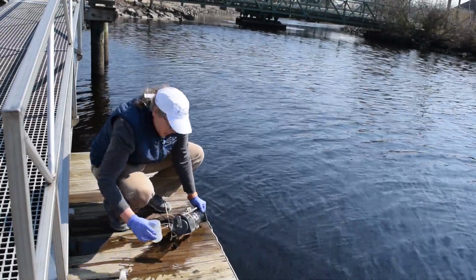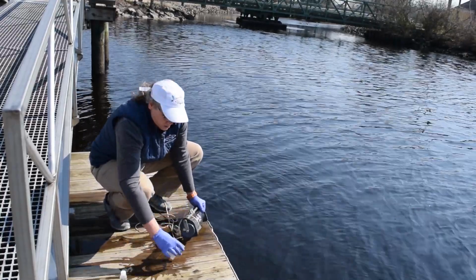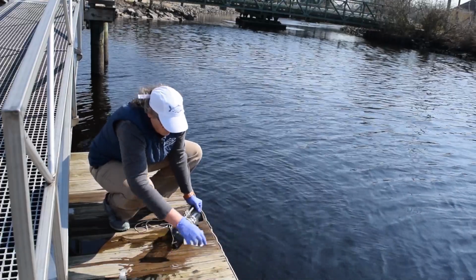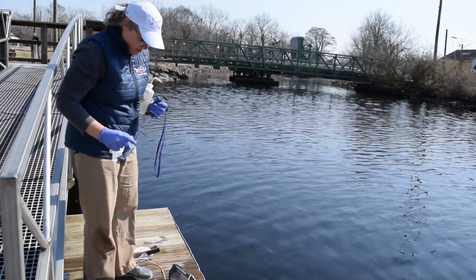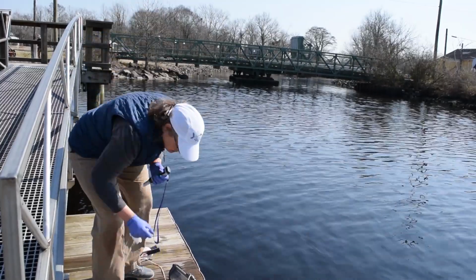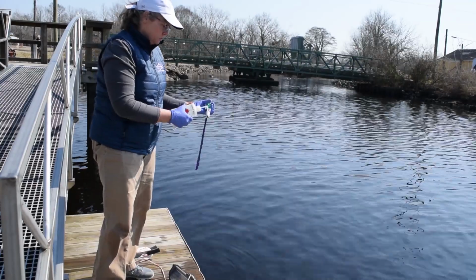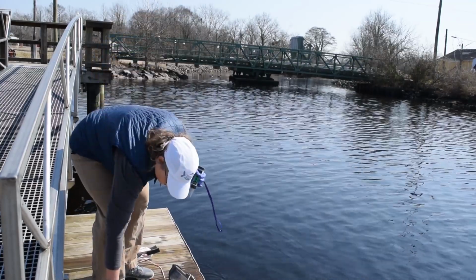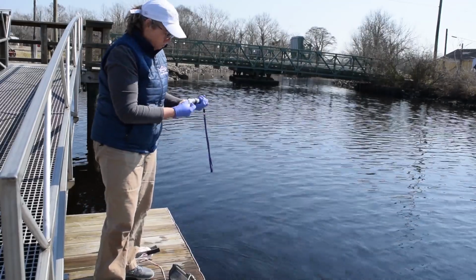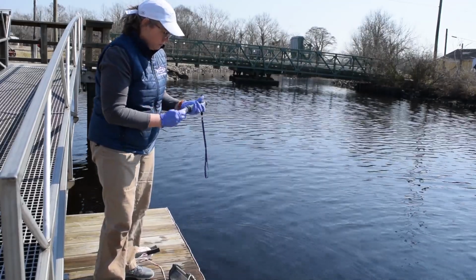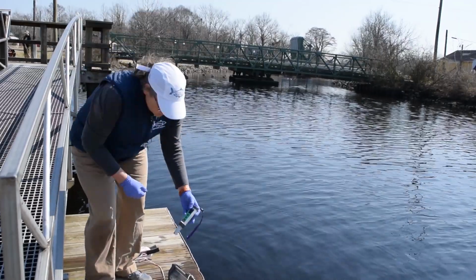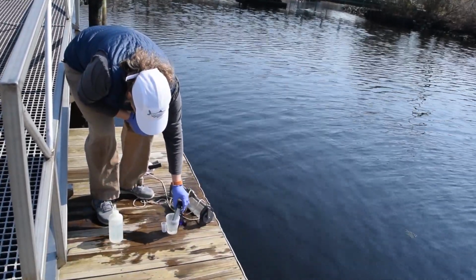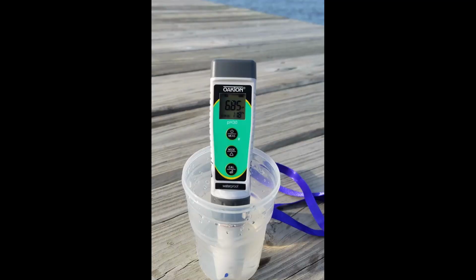Flush the empty ball jar with sample water 3 times. Put 50 milliliters of sample water in the jar. Then turn on the pH meter, rinse off the probe with distilled water, and thoroughly wipe with a Kimwipe. Next, place the pH meter in the ball jar, swirl it in the water, and allow the meter to sit until the value stabilizes. Note, in colder weather, this process will take longer, up to a minute or 2. In summer, the value will usually stabilize within 30 seconds.